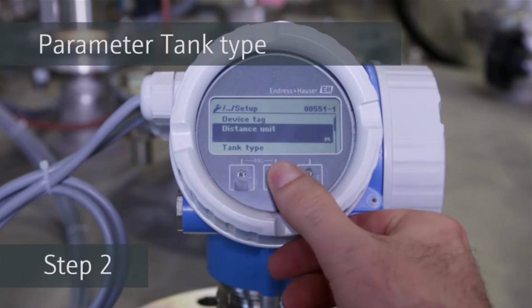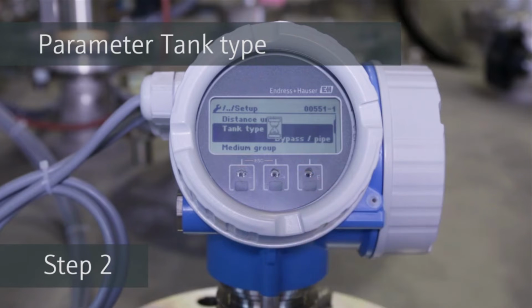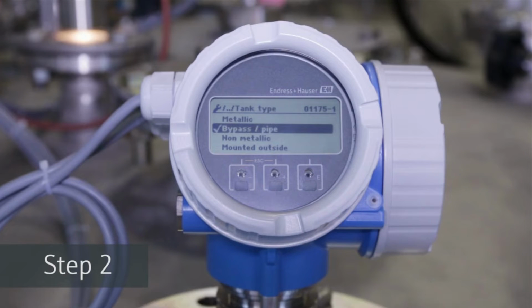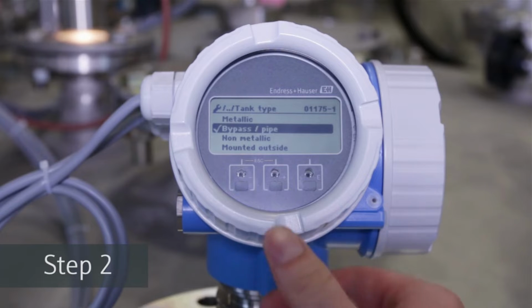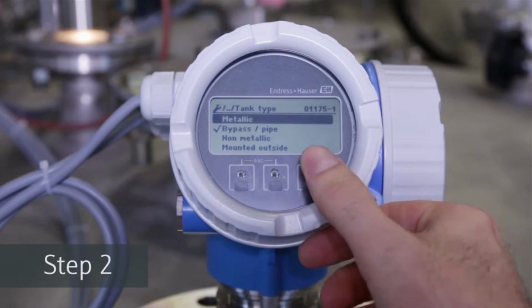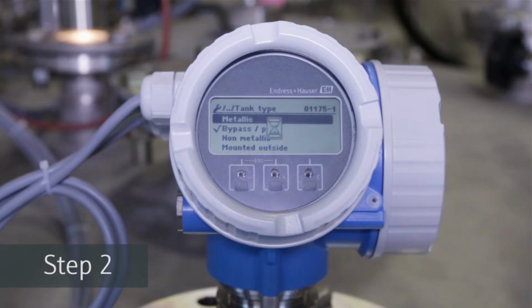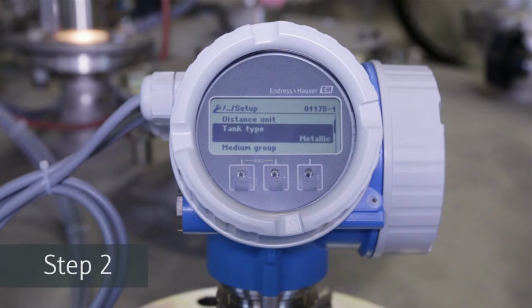The next step is related to the selection of the tank type according to your application. Depending on the probe type of your sensor, the selection of the tank type may vary, for example, for coax. In our example, we select the option Metallic. For Micropilot, the menu provides a selection of tank or bin types which are adapted to free space radar applications.